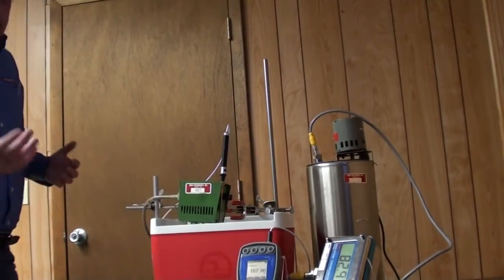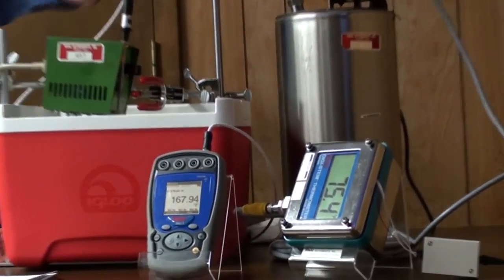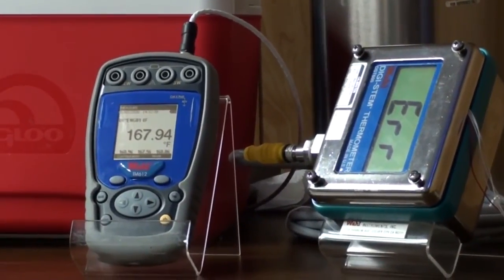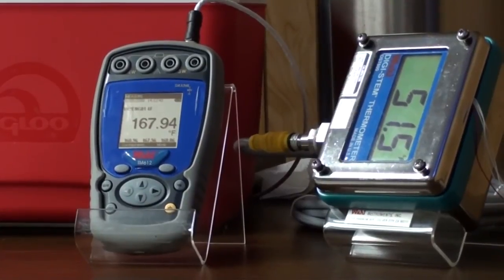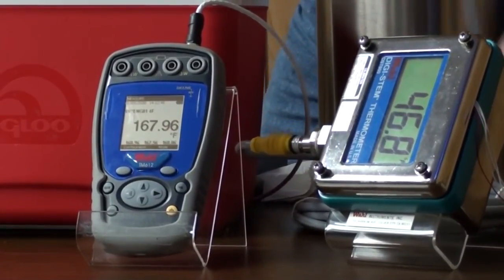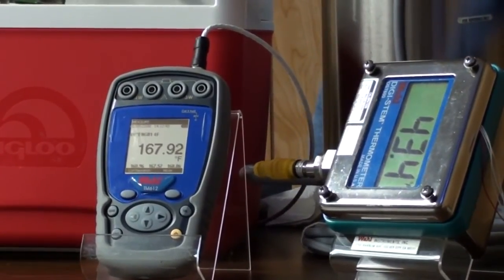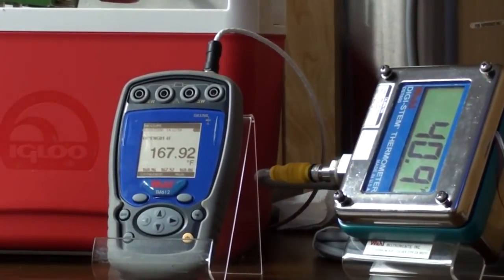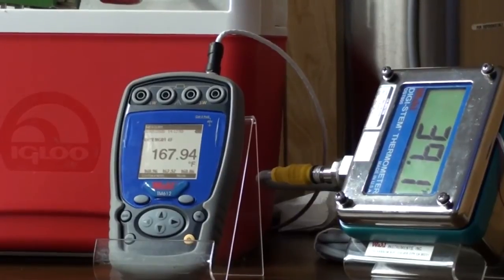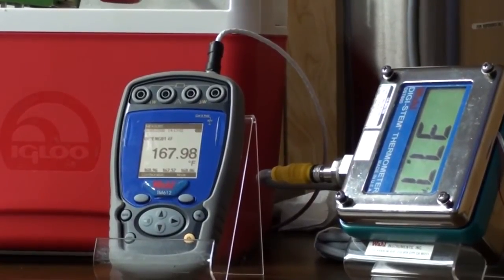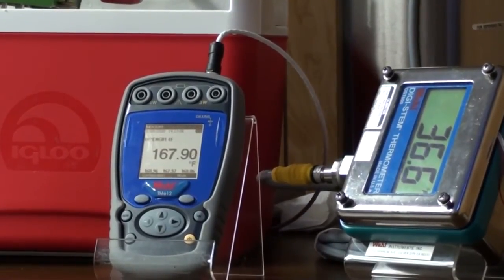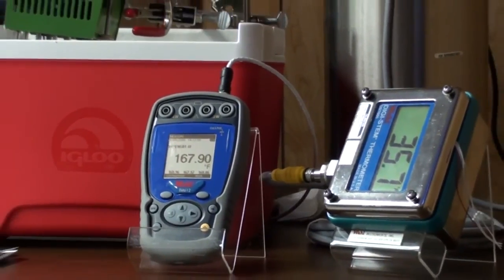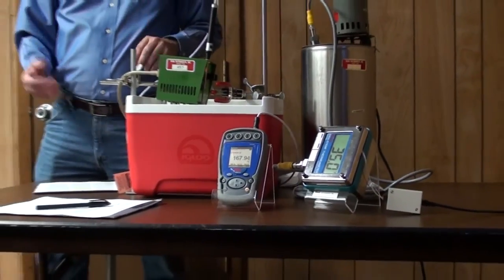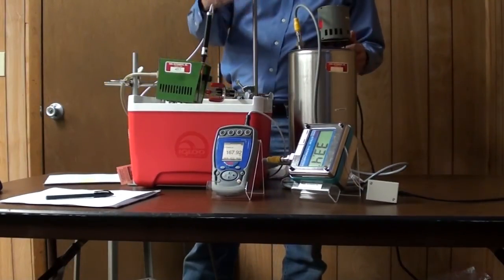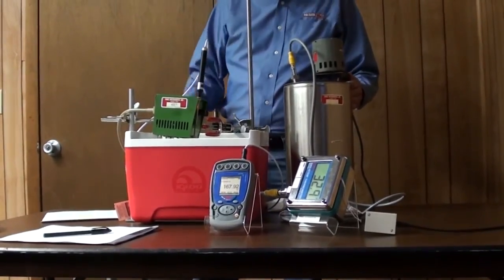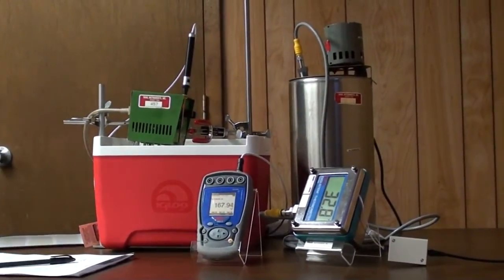You may notice that it said ERR, and if you use our units you'll see that. When we're going through an extremely rapid temperature change, I just plunged this into ice. We have error detection circuitry in there that checks the electronics, and the method it does that by is measuring the current through an ultra precise resistor, and then measuring some other ultra precise resistors that simulate temperatures at 180 and 250, I believe it is. And if it sees an error in that, it will display ERR on the screen. If it displays ERR and stays there permanently, there's a problem with the electronics. That doesn't happen very often. So I'm going to turn the ice bath on, and then once that's stabilized, we will do the calibration. Yeah, that's not too loud. I'm sure you can still hear me.